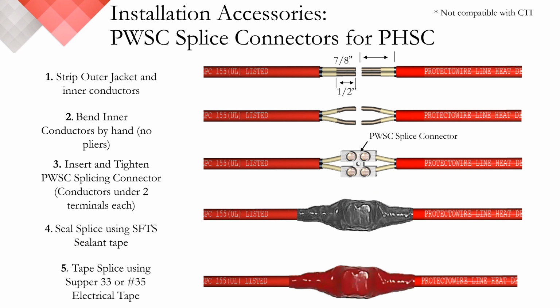Another convenient aspect of linear heat is your ability to make repairs to the detector. This is accomplished first by identifying the location of the fault. Depending on the facility and the application, there could very well be more than one fault location. Once these areas are located, you can follow these instructions to properly remove and splice in the new section of detector. For PHSC and PLR series, we follow the steps illustrated here. Since we're working with steel conductors, the use of our PWSC splice connector is required. A copy of these instructions are also available on our website.